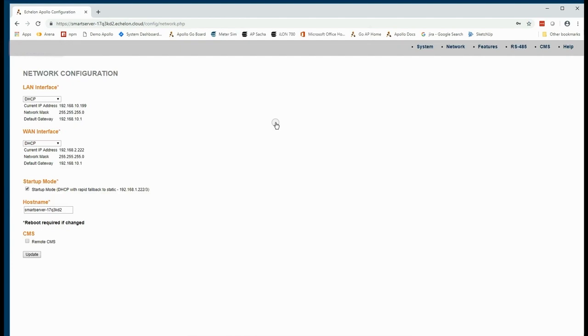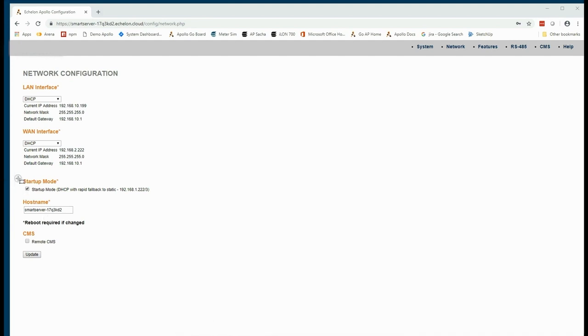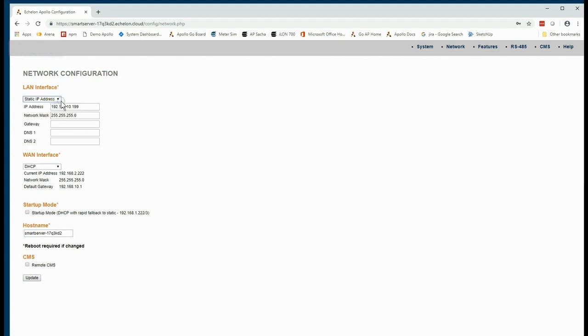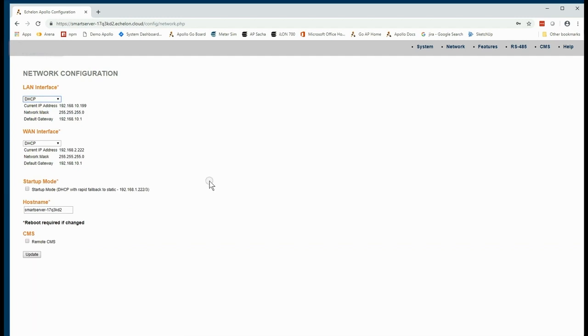When we first log in, we're going to see the overall system configuration, and you'll see here that it's set up to be in startup mode. It's from this network configuration page that we want to establish exactly how we want to operate this Smart Server. Normally, we uncheck startup mode and select between DHCP and static addresses according to how we want to manage the Smart Server in our internal network.